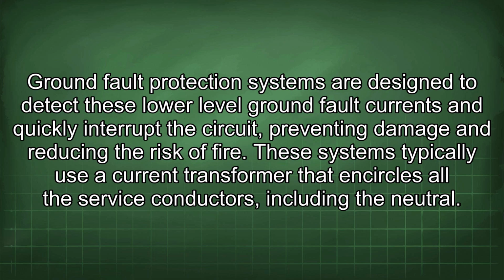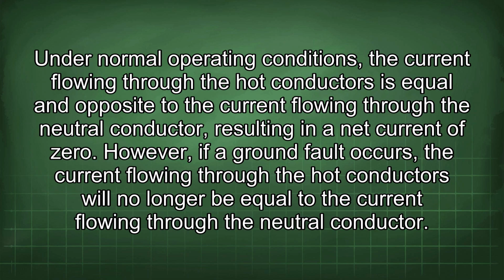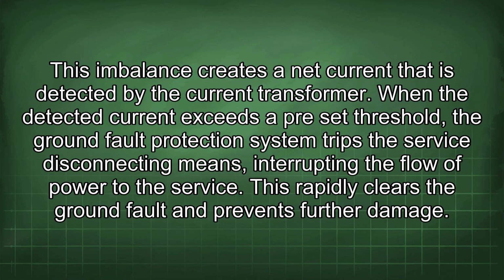These systems typically use a current transformer that encircles all the service conductors, including the neutral. Under normal operating conditions, the current flowing through the hot conductors is equal and opposite to the current flowing through the neutral conductor, resulting in a net current of 0. However, if a ground fault occurs, the current flowing through the hot conductors will no longer be equal to the current flowing through the neutral conductor. This imbalance creates a net current that is detected by the current transformer. When the detected current exceeds a preset threshold, the ground fault protection system trips the service disconnecting means, interrupting the flow of power to the service. This rapidly clears the ground fault and prevents further damage.